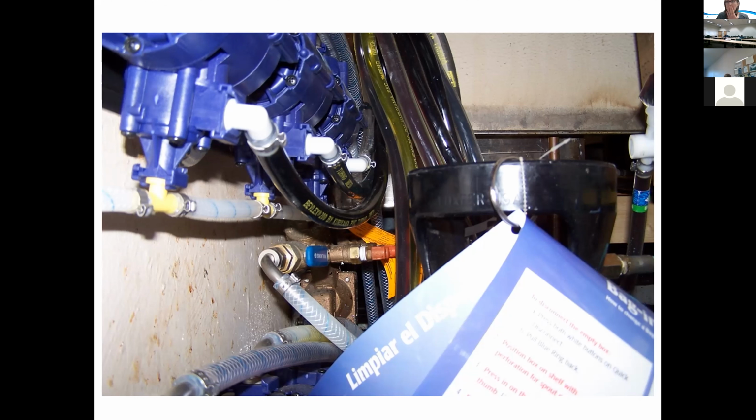Another fun one, from about a year ago: one of our larger municipalities had a gas station that called about air coming out of their water lines. They went out there and took a look, and the CO2 tank in the back was all frosted over.